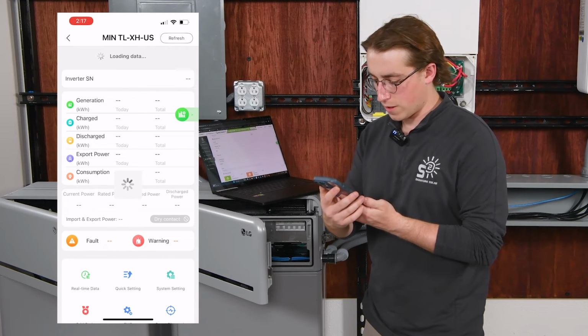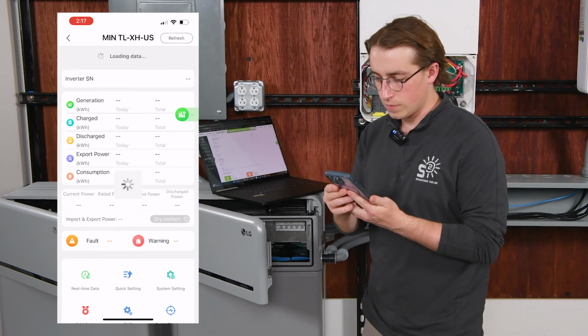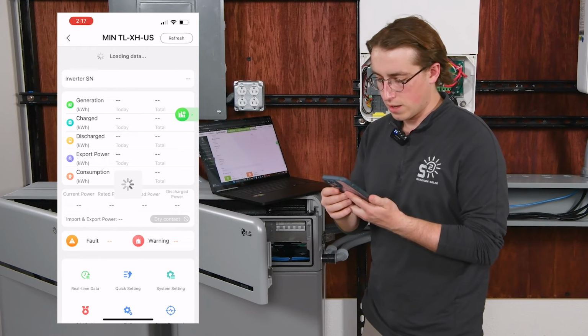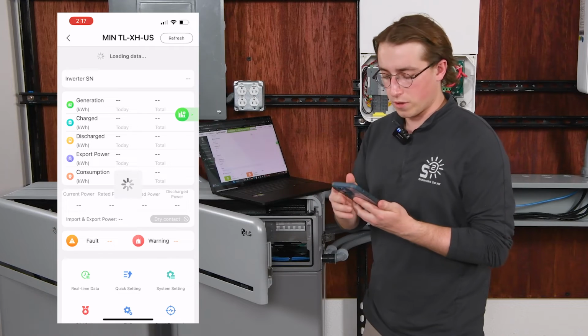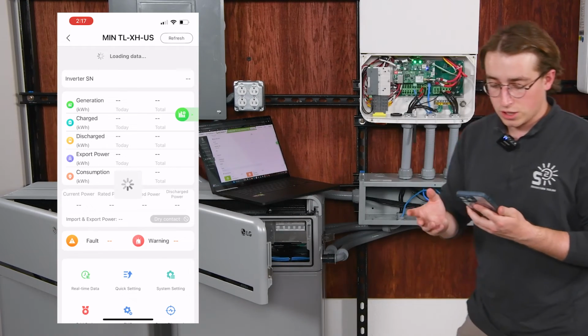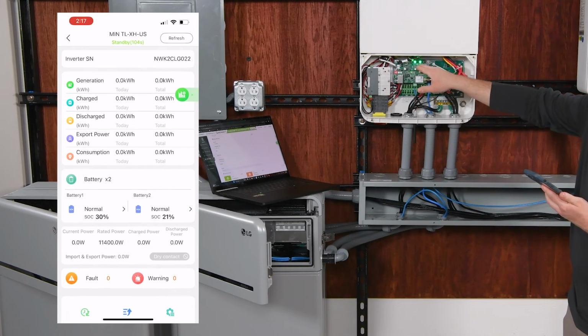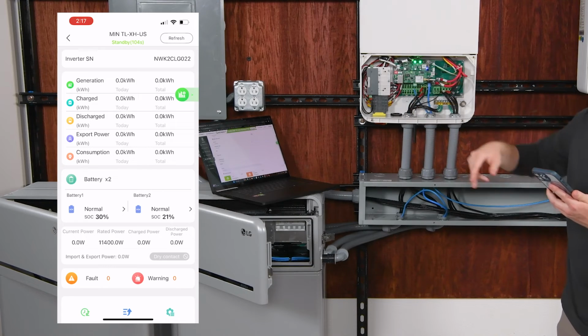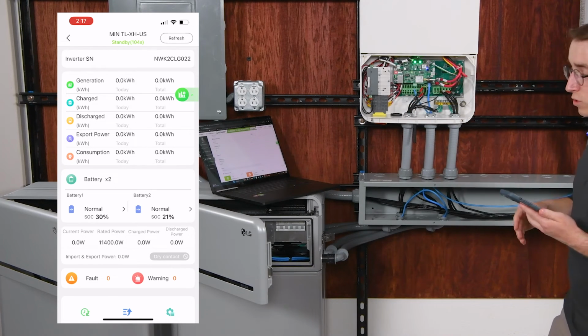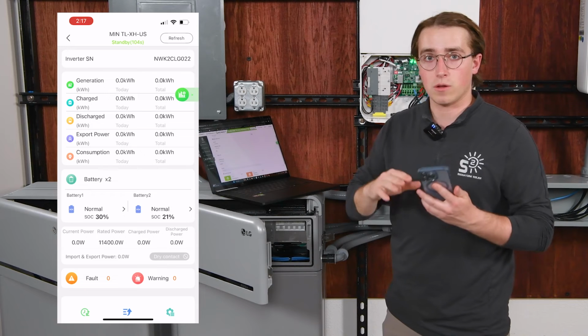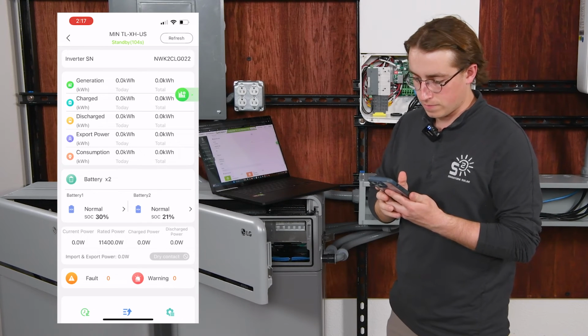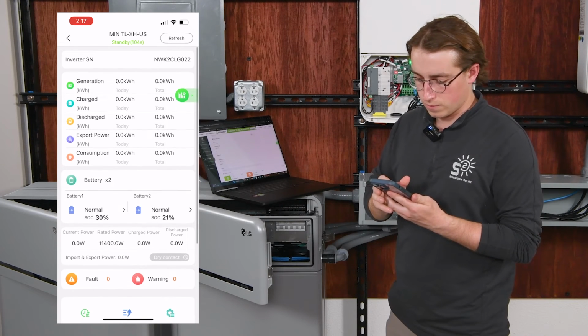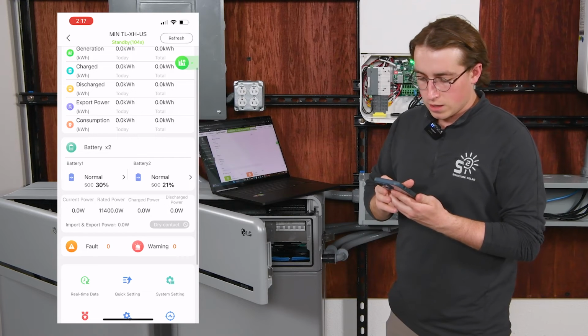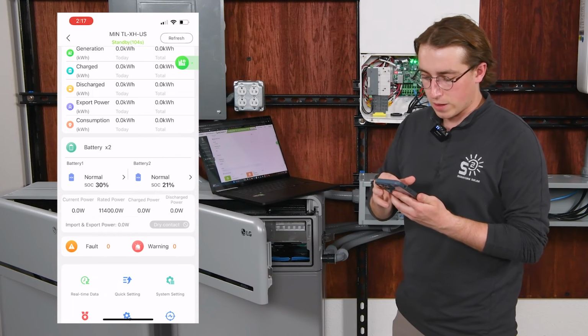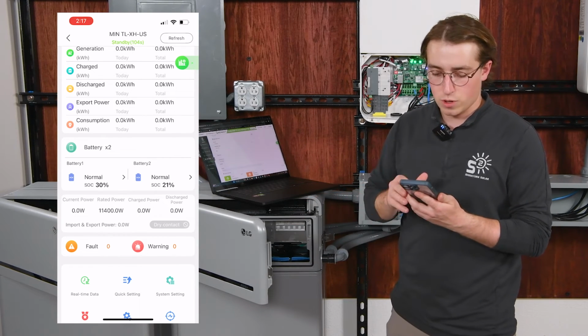We're on the main home screen here. And once it loads all the data, we should see if there are any fault or warning codes with the system. Additionally, if there are any fault or warning codes where the LEDs are here, we should see a red LED. And once we put the face cover back on, you can see all the indicators that are there. Perfect. So it looks like we are reading the LG batteries here, which means our communication is set up properly.